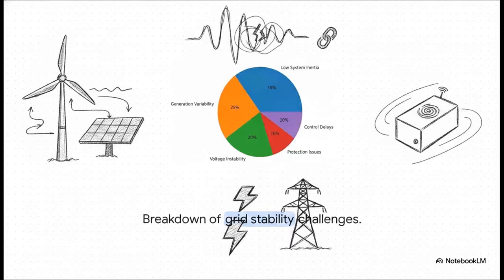And this brilliantly illustrates the real-world impact of that dropping inertia. In high renewable systems, low system inertia now accounts for a staggering 35% of overall grid stability issues, followed closely by generation variability and voltage instability. This disappearing inertia is completely forcing the hand of grid engineers. They're having to invent entirely new mitigation techniques, like grid-forming inverters and virtual inertia control, literally just to keep the lights on and the system stable.